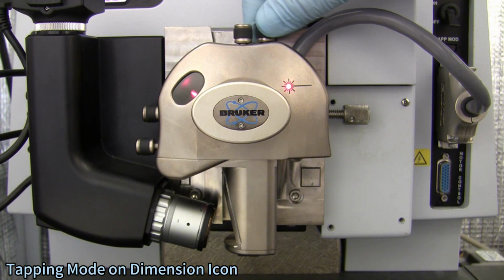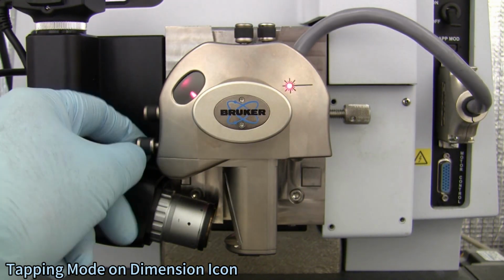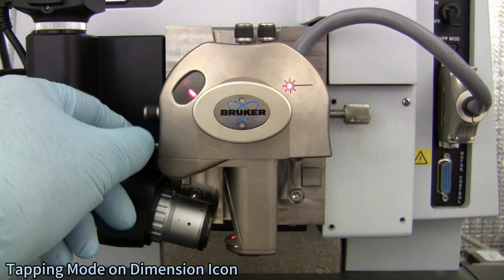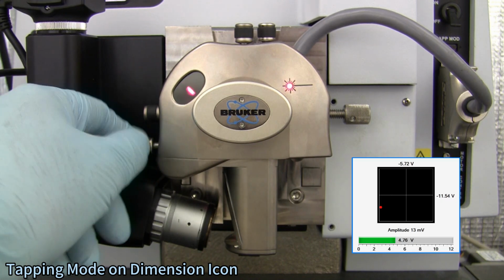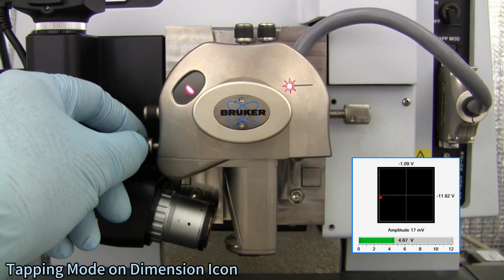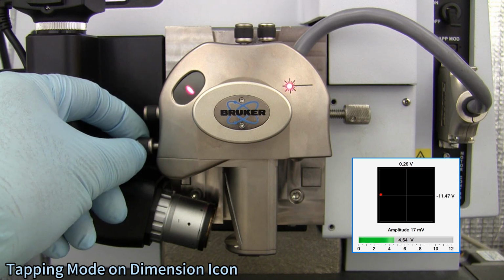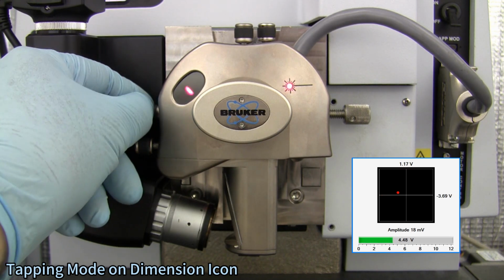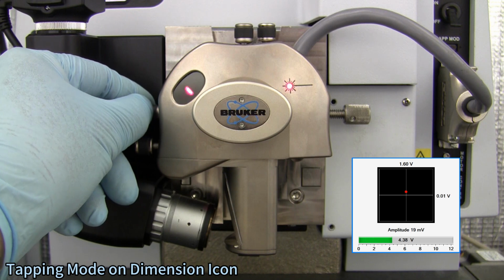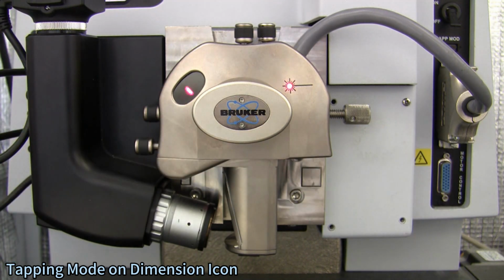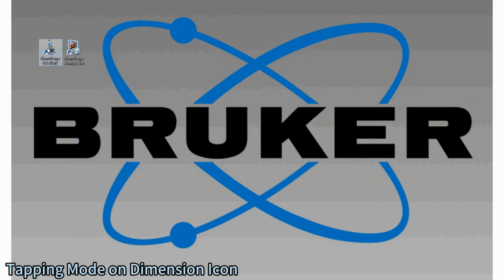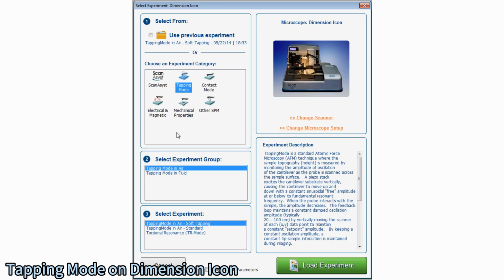Align the laser onto the probe and into the detector using the shadow method or the alignment station. For a detailed explanation of the probe alignment and laser alignment process, watch the separate video entitled Aligning the Laser on Dimension Icon. Launch the Nanoscope software and select tapping mode from the configuration menu.